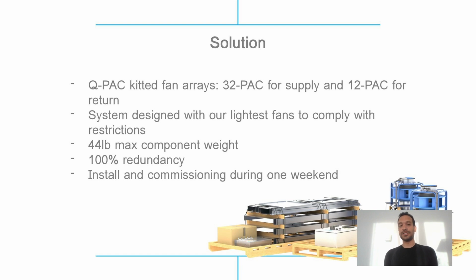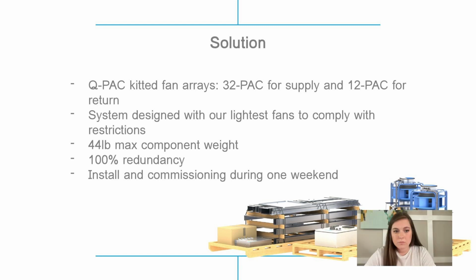Because of the weight limit, we had to go with pretty small fans that would fit in that weight limit for the government. So we had to go with a lot of fans, especially on the supply side, that the static was pretty high. On the return fan, we had to go with 12 fans. So very large fan arrays, a lot of fans to be used, just to comply with that weight limit that they had.